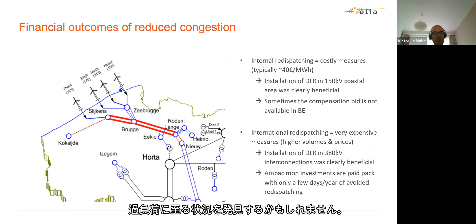They might see that in some situations a specific line is overloaded, and you always have the question: should I structurally increase my grid, or use a temporary solution like a dynamic line rating solution? You can detect in advance where the bottlenecks are and where lines are heavily loaded. When we see in grid development calculations a line with an average high load, even if manageable just under the static rating, we might still consider installing dynamic rating, because you never know what will happen 5 years later. When you're too close to the static rating in your calculation, it's good advice to consider it.